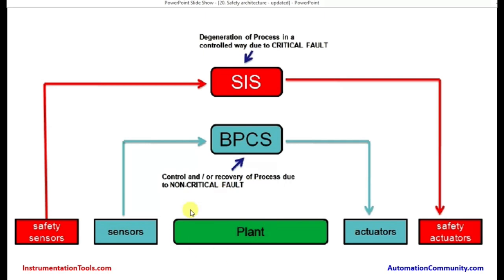This is a plant process having different sensors and different actuators. BPCS stands for basic process control system — it controls and recovers the process due to non-critical faults. During normal operation, the plant is under control by the BPCS. In case of any alarm — for example, if measuring 0 to 10 meters in a vessel and at 7.5 meters it gives a high alarm — that serves as a preventive measure in order not to exceed the level limit.